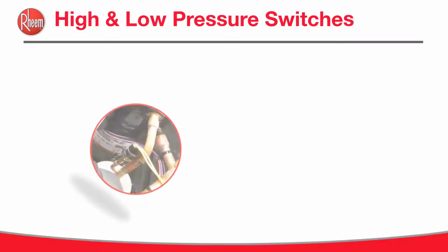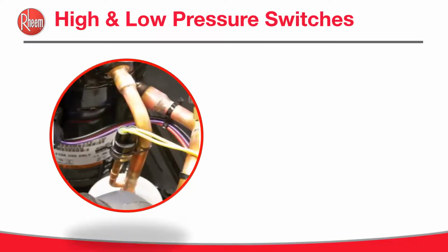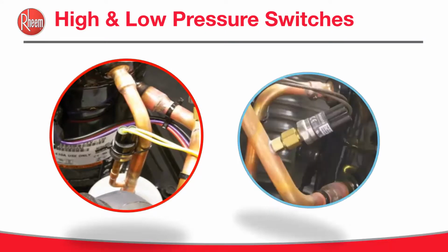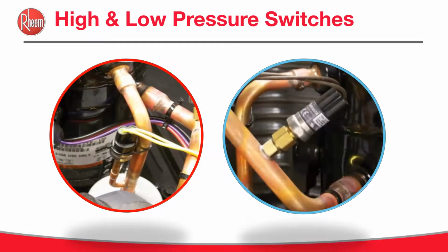So let's look at high and low pressure switches. High and low pressure switches may be present on the AC units, but are not required. But they are required for heat pumps. We do require high and low pressure switches. The high pressure switch opens at 610 PSI, and closes at 420. And the high pressure switch can open due to an inoperable fan, an overcharged system, and a dirty outdoor coil.